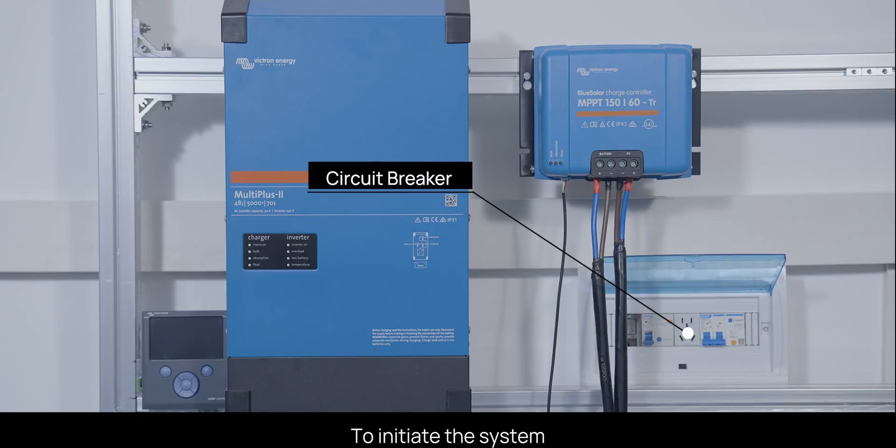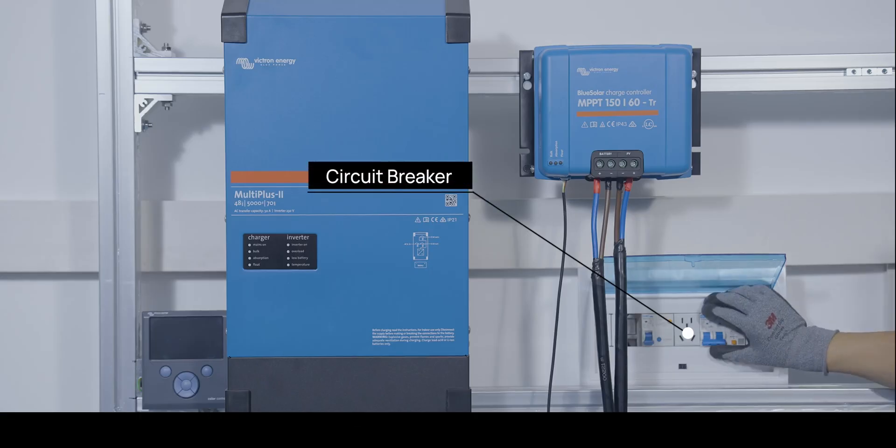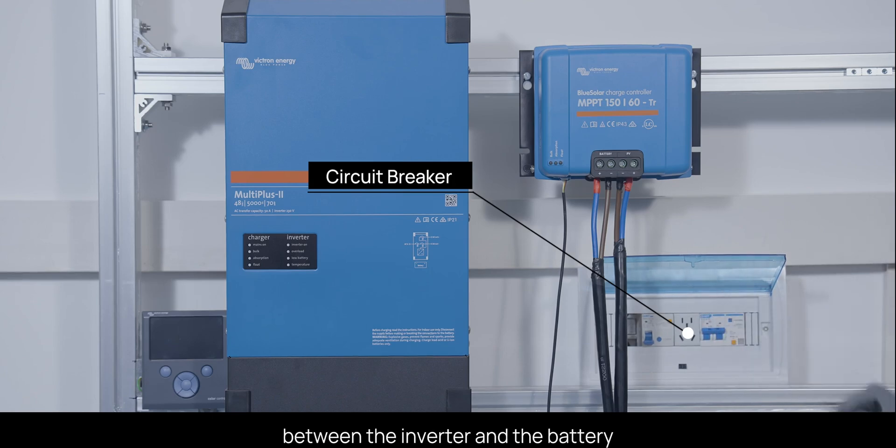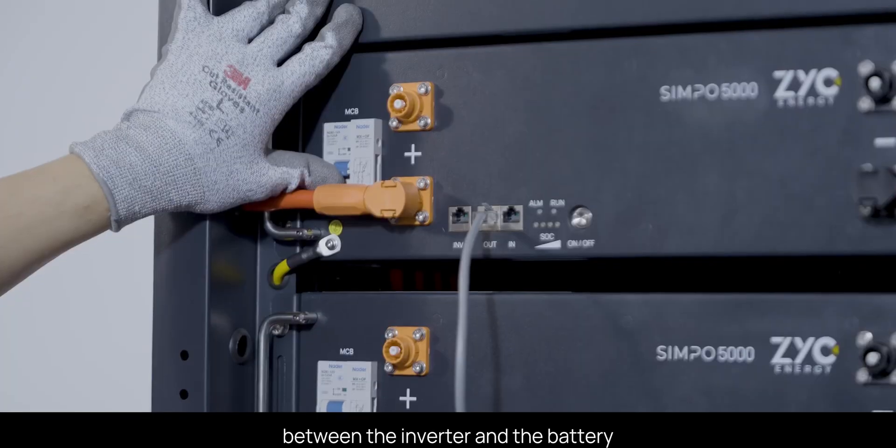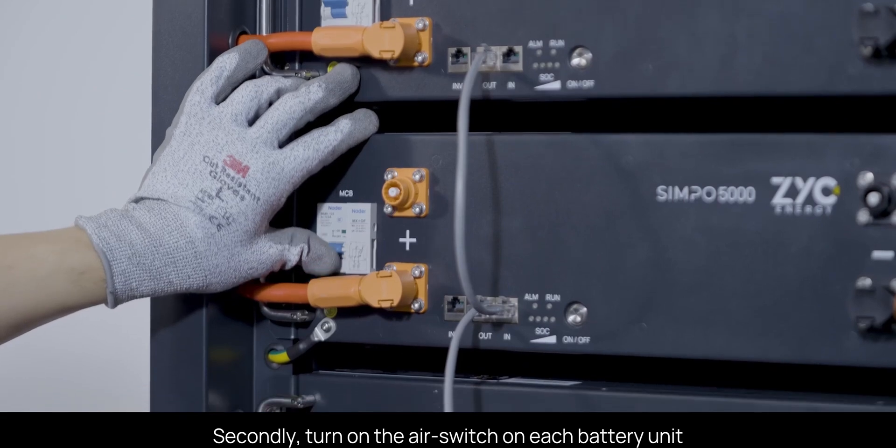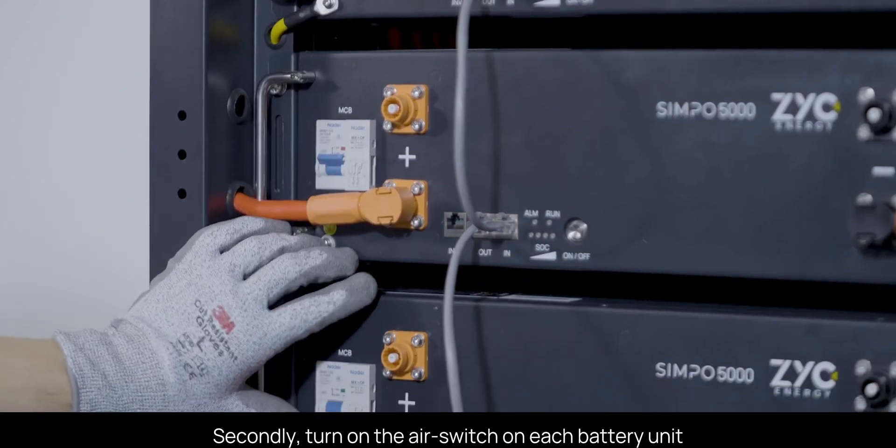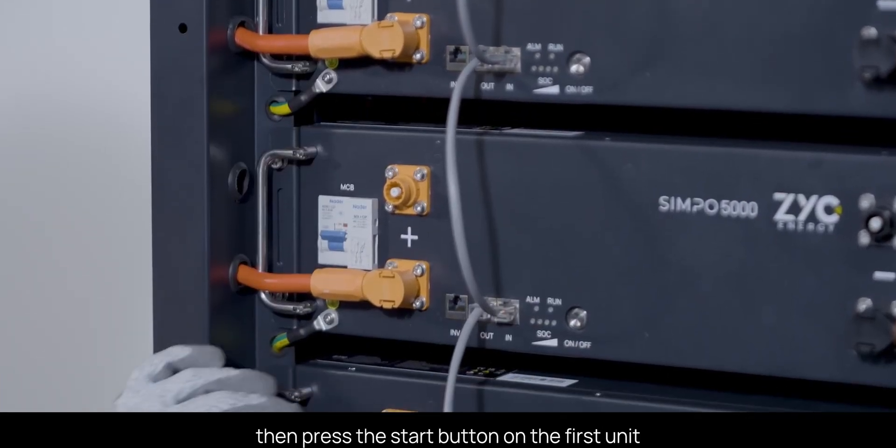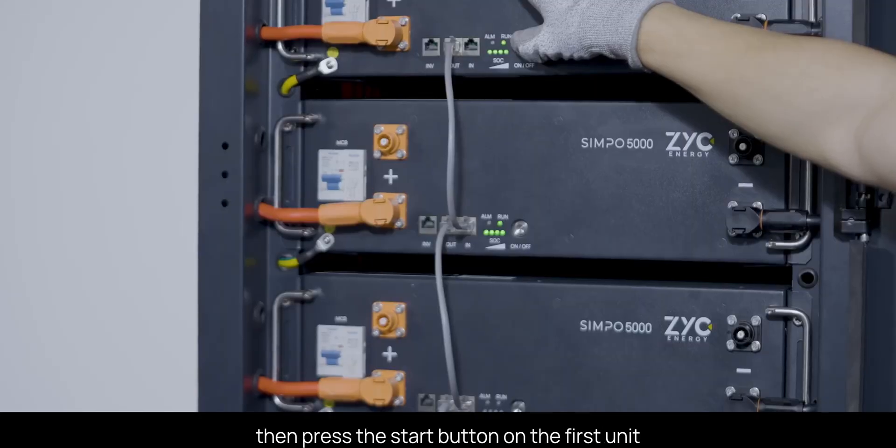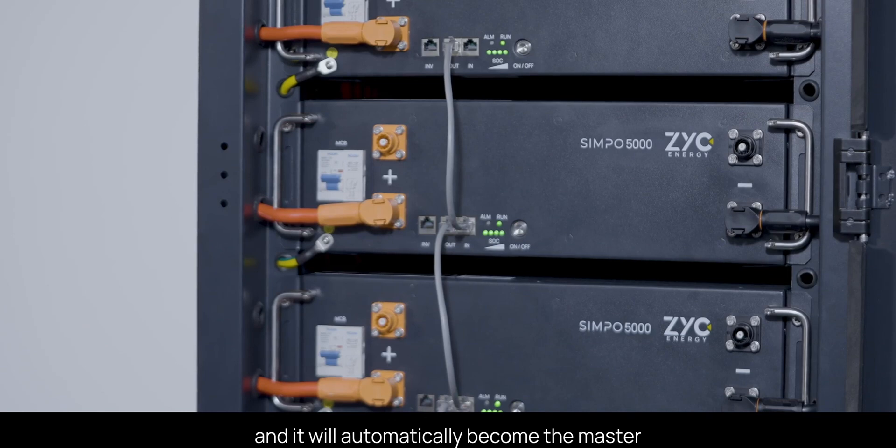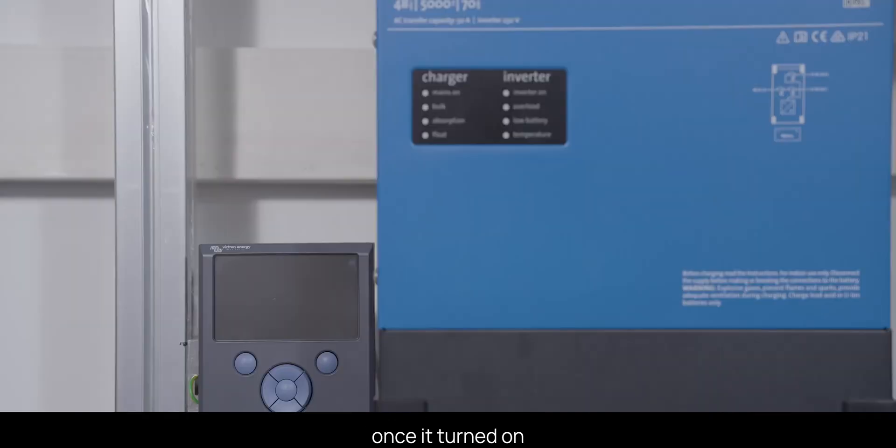To initiate the system, first, activate the circuit breaker between the inverter and the battery. Secondly, turn on the air switch on each battery unit, then press the start button on the first unit, and it will automatically become the master once it's turned on. Switch on the inverter.